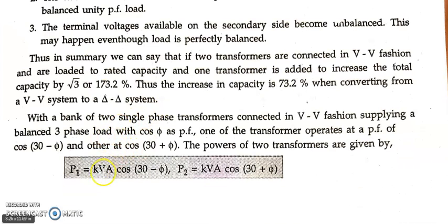So here the formulas are given. The power of the two transformers that are connected in open VV connection: first formula is P1 equals kVA cos(30 minus phi), P2 equals kVA cos(30 plus phi). One will operate at cos of 30 plus phi, whereas the other one will operate at cos of 30 minus phi. Okay, you need to remember this, it will help while solving the problems.